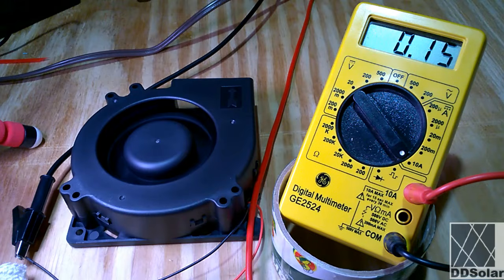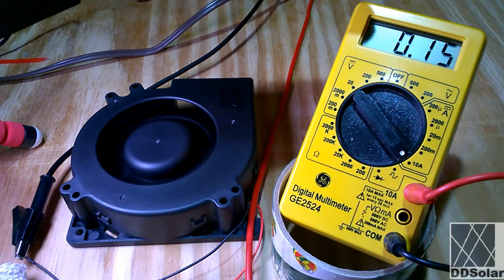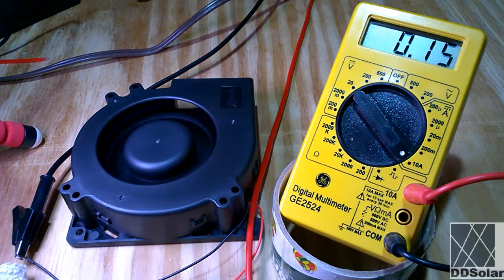And now you can see that the fan has turned on, and it's drawing about 150 milliamps, or 0.15 of an amp. 150 milliamps is a very small amount of current, and I can leave this meter attached all day. As long as the battery in this meter doesn't run down, it's perfectly safe. There's not going to be any heat generated. That is a very, very small amount of power.